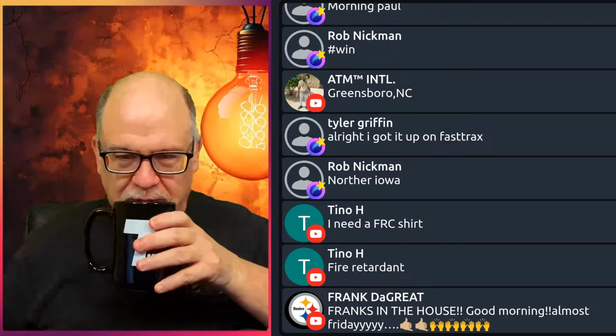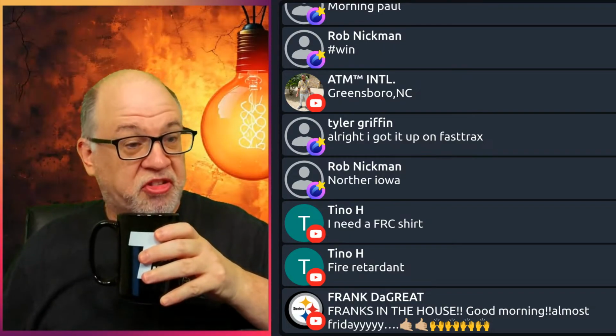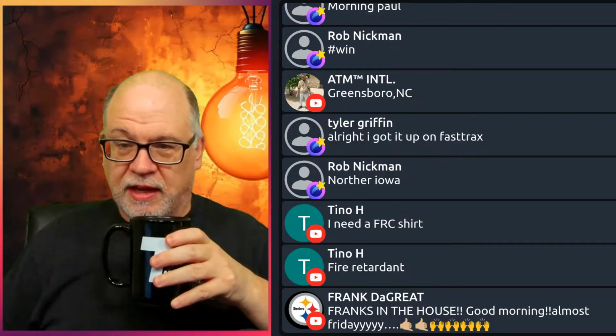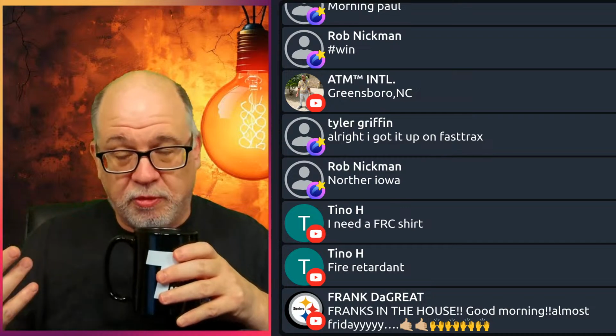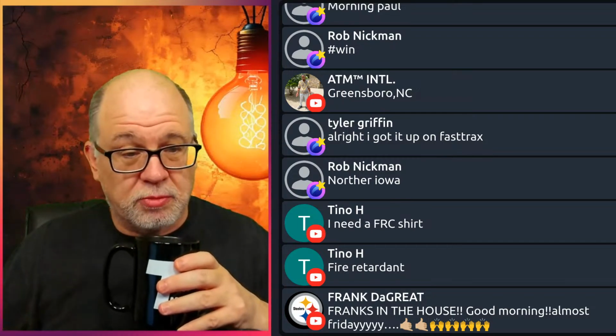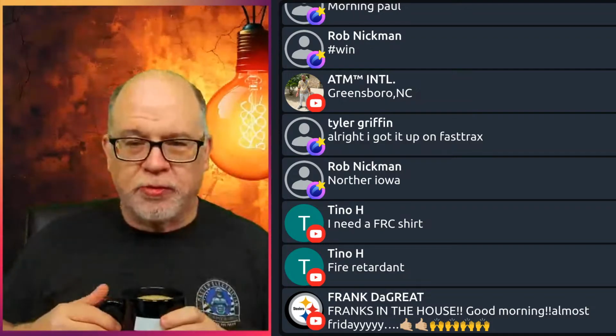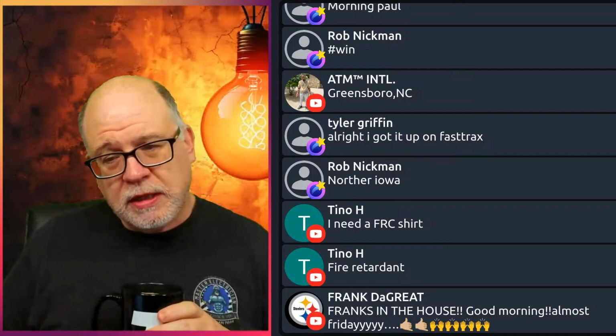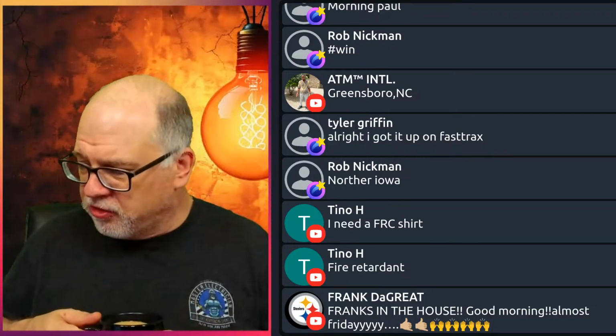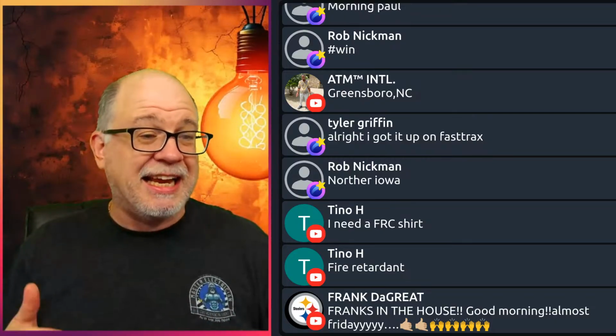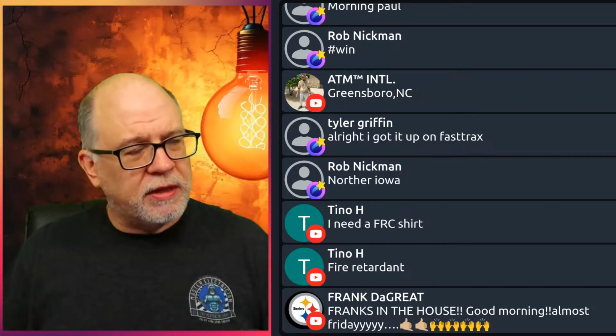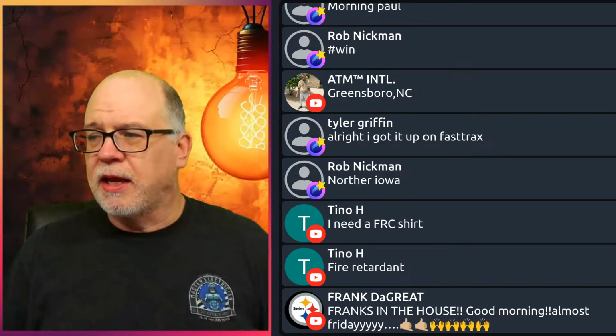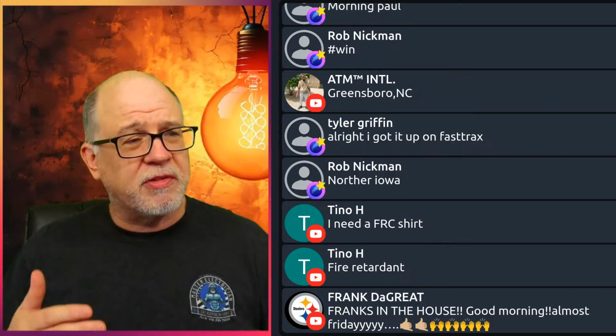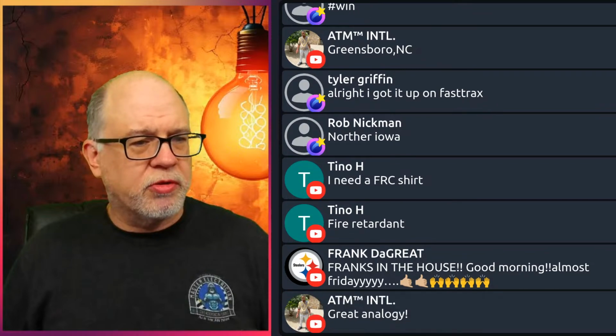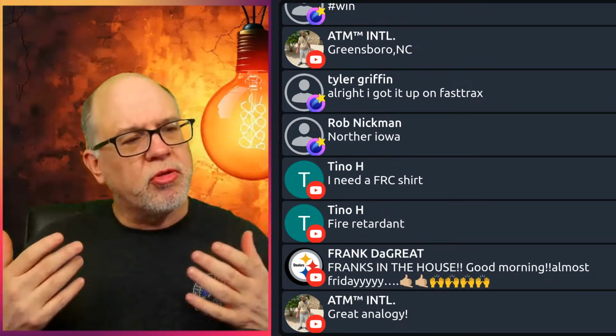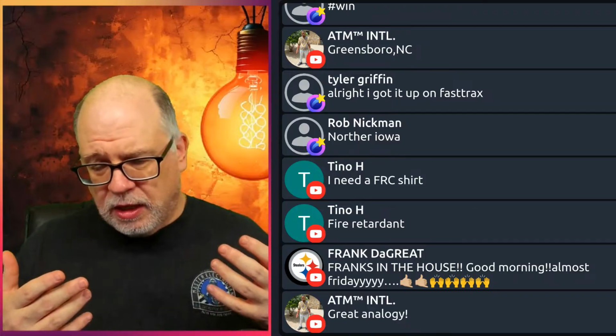Now, let's talk about some main concepts. We have the grounding electrode system. That is a system that includes things like ground rods, water pipe grounds if you've got them, concrete-encased electrodes, with UFERs, that type of thing. UFER, people ask, what's a UFER? It's actually just slang for a concrete-encased electrode. A lot of the original testing on the UFER was done by a guy named Herb Ufer. And he wasn't the only one. There were also engineers, inspectors, and people like that around the country, especially on the West Coast, who helped contribute to the understanding of what a UFER ground was.